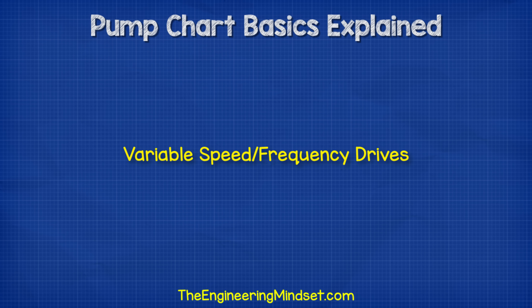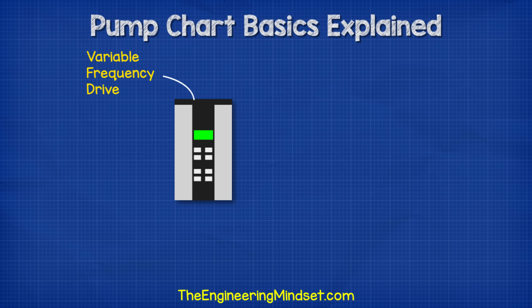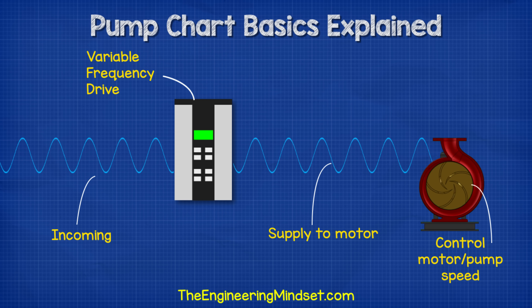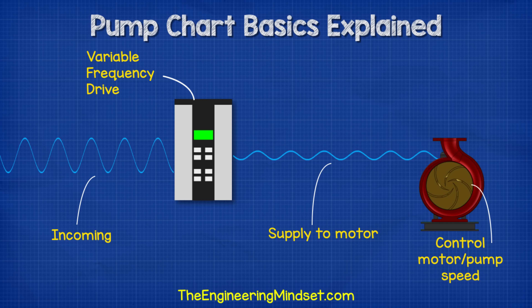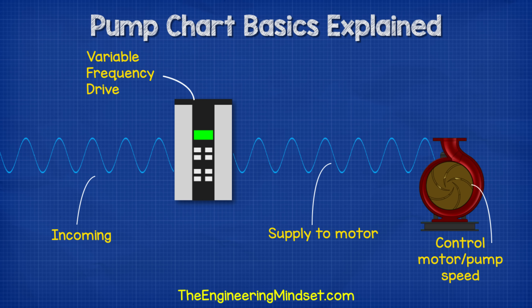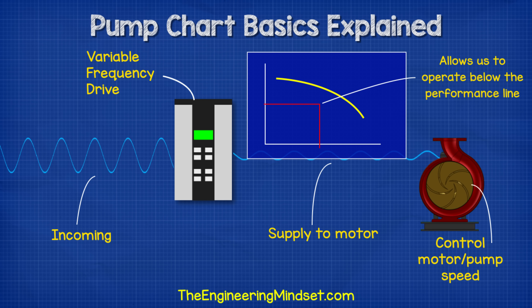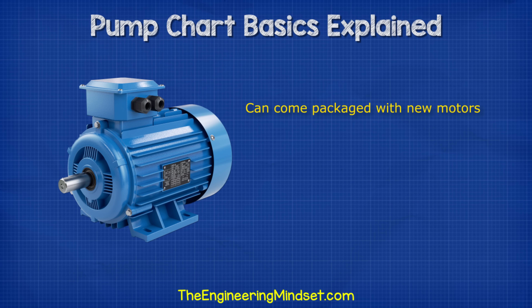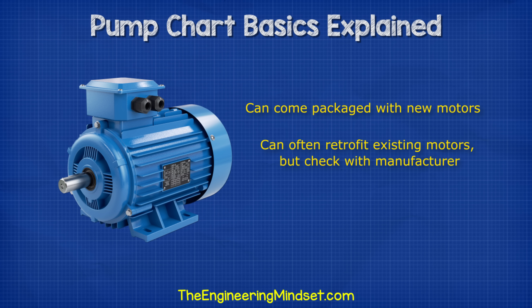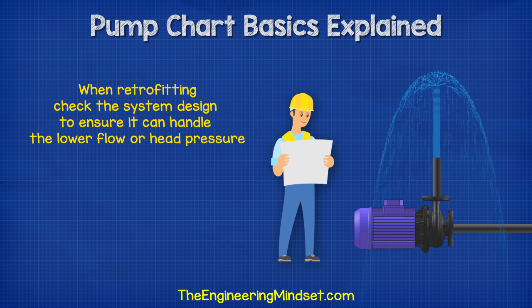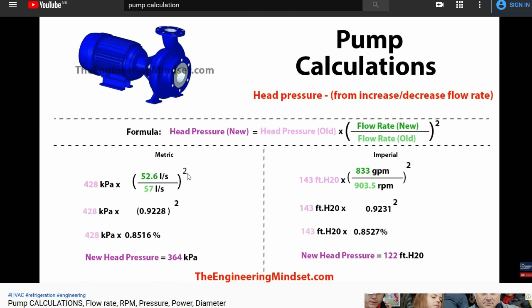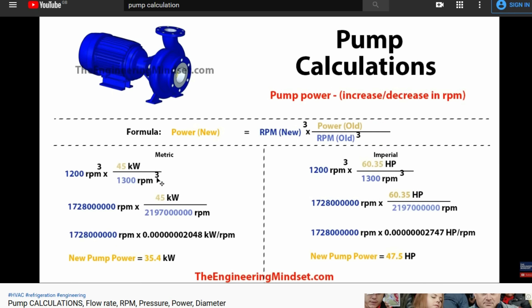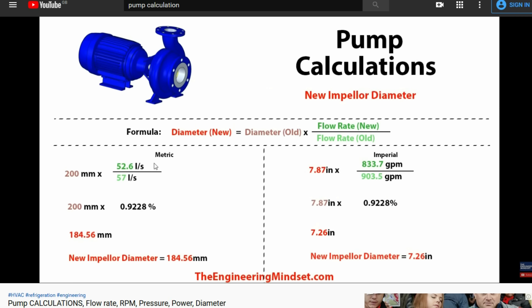Variable speed or variable frequency drives. Another option we have is to use a variable frequency, or variable speed drive. This basically takes the electrical supply and alters it to reduce the voltage and frequency, which therefore alters the power of the motor and the speed of the pump. We can increase or decrease the speed via the controller to better improve our pump match and therefore operate nearly anywhere in the region below the curve. These are only really used on larger pumps, typically over 2kW in size. They do come pre-installed with new pump motors or you can also retrofit existing pumps, but you should check with the manufacturer first to ensure compatibility. You must also check the system design to ensure it can handle a lower flow rate and head pressure. To obtain the performance details for variable speed pumps, we have to calculate the values using the pump affinity laws — we've covered this previously in worked examples, links down below.